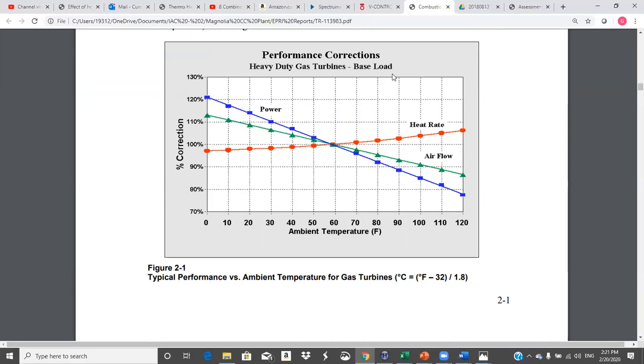So this shows, it picks a 60-degree ambient as the 100%, kind of like the point of comparison. And so you see, if you just decrease ambient temperature from this point of 100%, look what happens to the power. I mean, if you put 0-degree air, you get an extra 20% power out of this guy. And airflow, this would be a mass flow because the CFM would be constant, but that's just the density increase of the air. You see, it's going up about 12%, and the heat rate is going down maybe about 3%. So see, cold is good for a gas turbine.